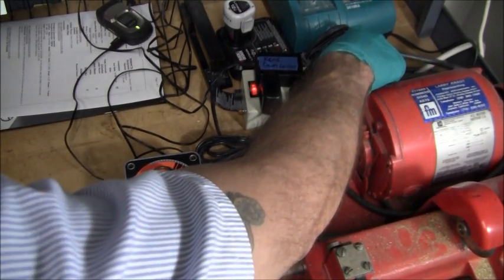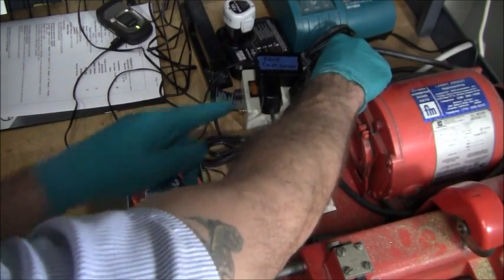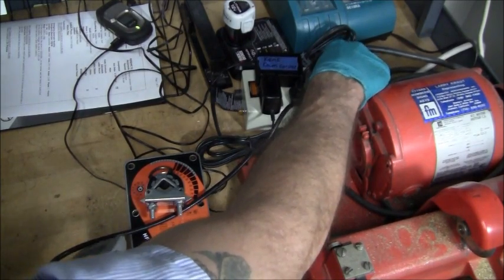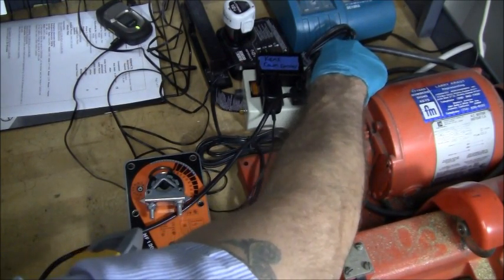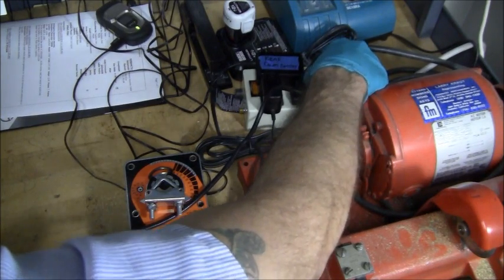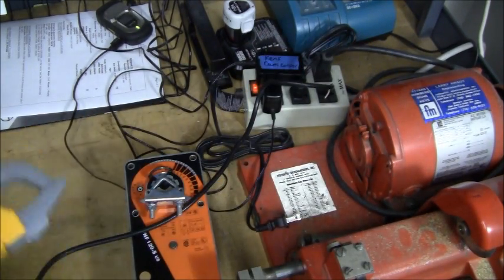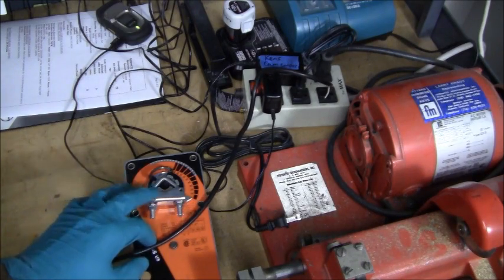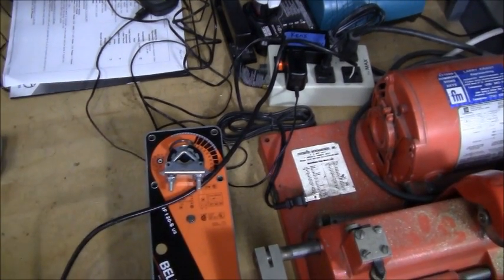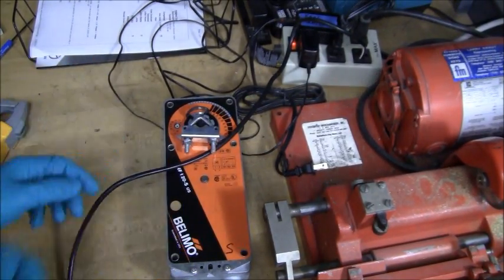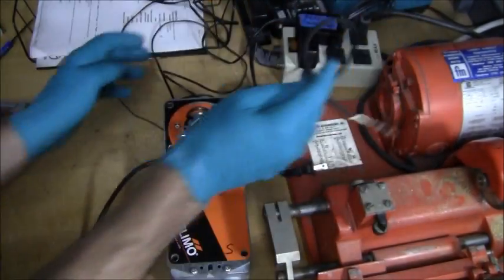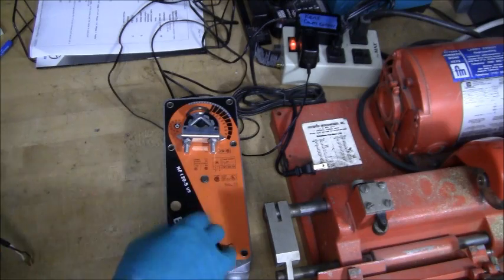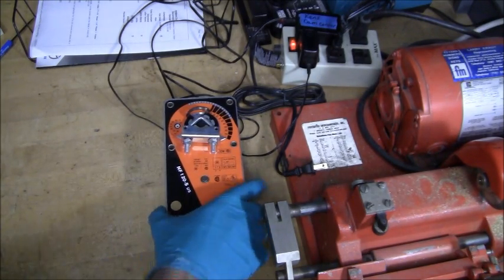I take my meter and go on NCV. So you know I've got 110 volts going to this. This is not moving. This motor and mechanism is bad. So we know this is the bad one. I already troubleshooted it. I was just giving you a tabletop demonstration on how to determine whether this fire damper motor is working or not. We know that this one is not working.